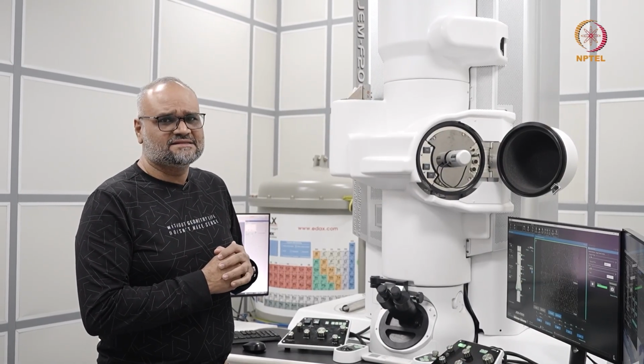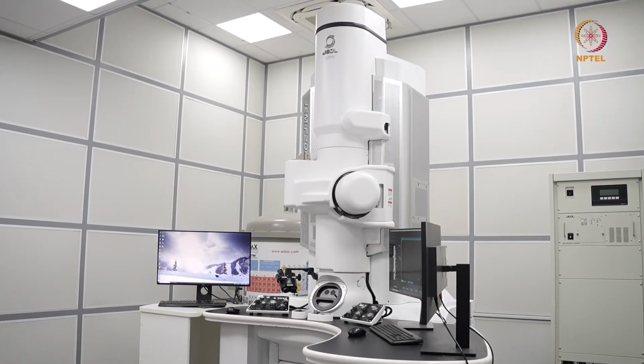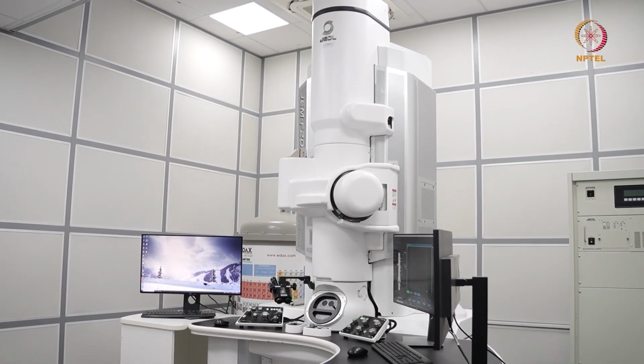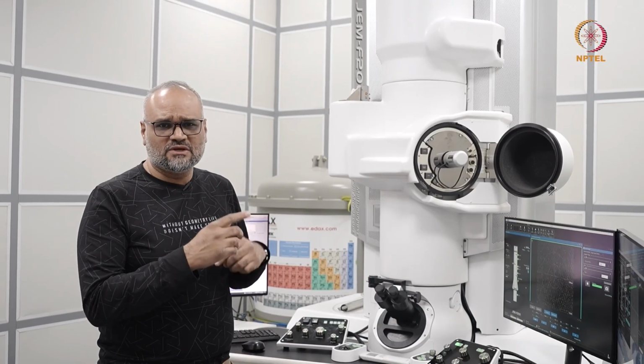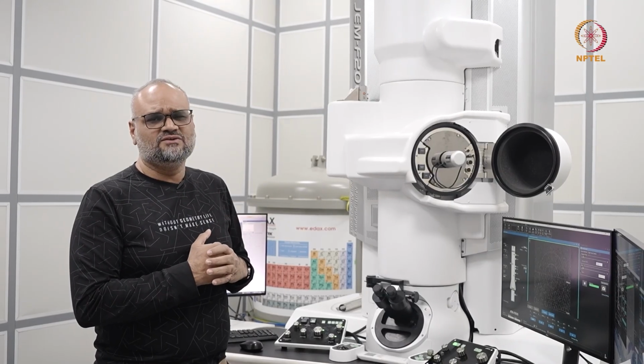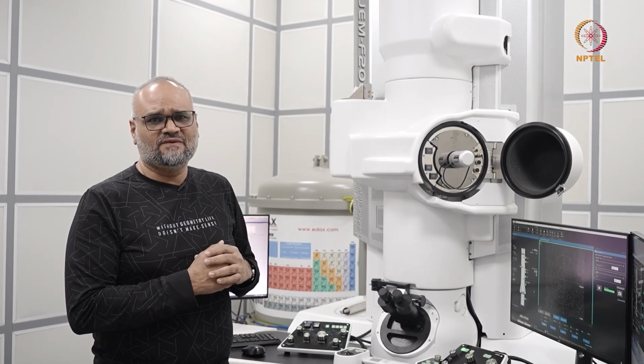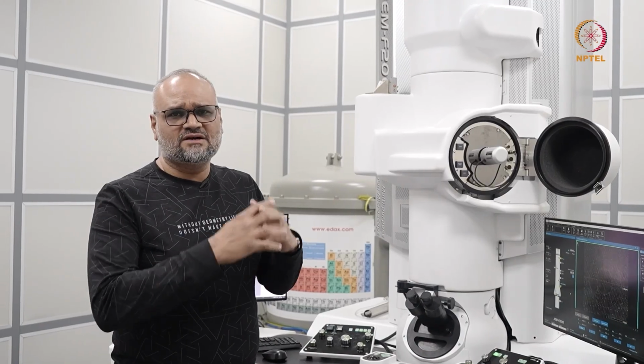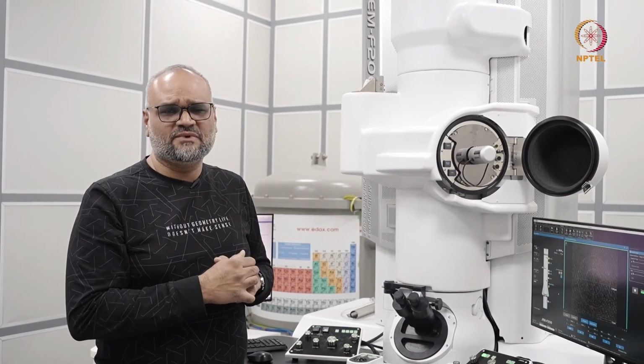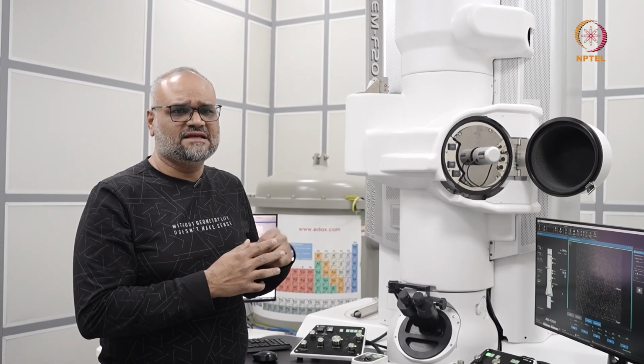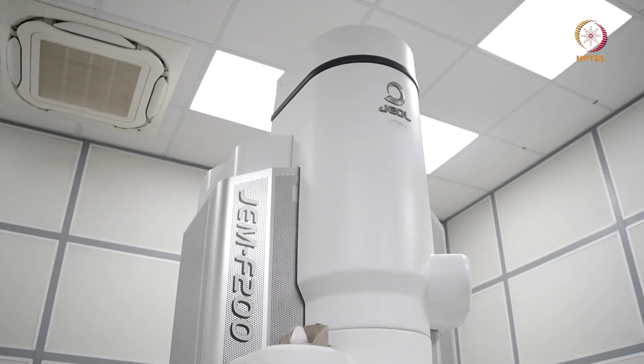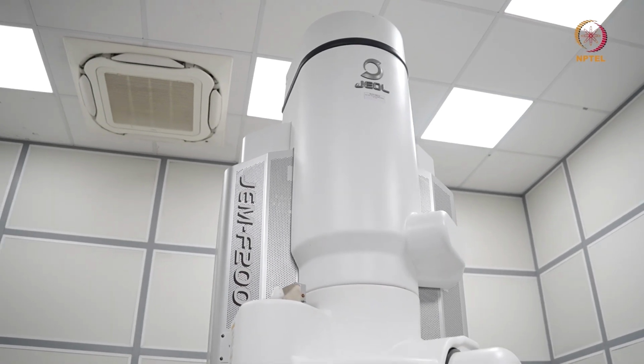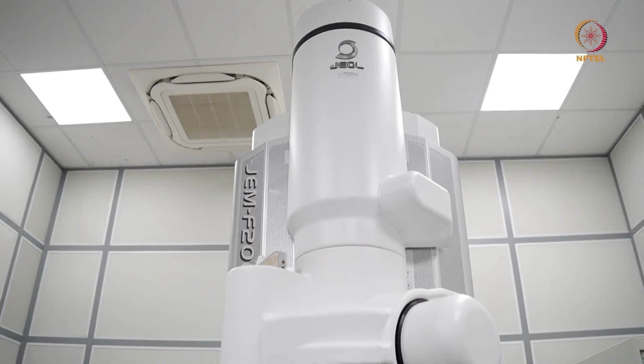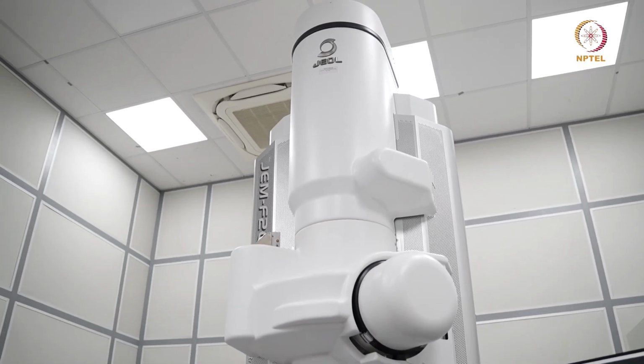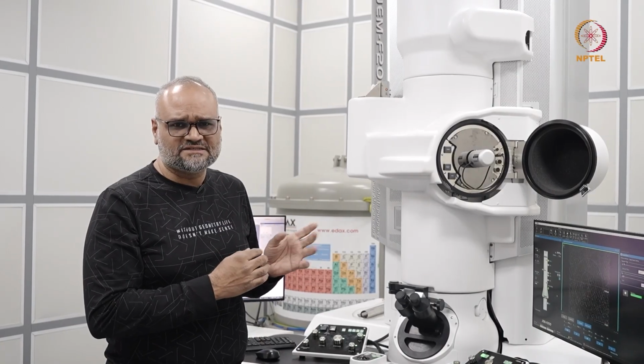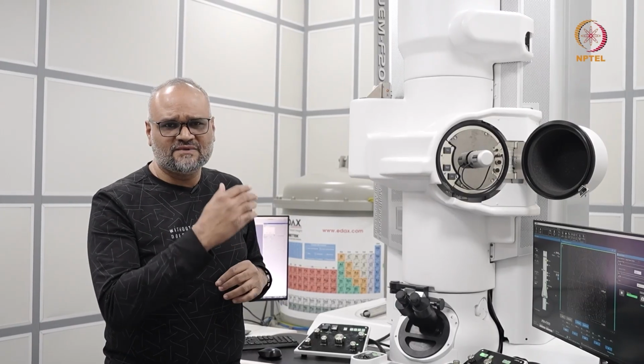So the idea is, this cold field emitter has a tungsten filament which is maintained at room temperature, and every day you want to use the instrument, you do a quick flash. So when you flash, what you do is you remove any oxide or a redeposited layer on the tip of the filament, and this is an automated process now. Earlier this was all manual control and through turning of many knobs, and it was more difficult to maintain a cold field emitter. But thanks to the automation now, you can actually do a flashing every day.